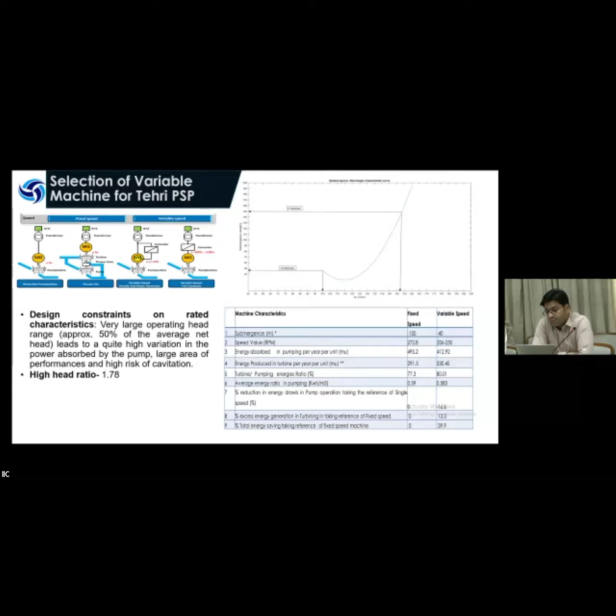Means in the case of fixed speed machines, we would have to excavate the powerhouse up to 250 meters for the setting of the turbine. By using variable speed machines, the submergence is only 40 meters. Also, the head ratio is 1.78. As per the report published by the CEA, variable speed machines are to be used for a head ratio of more than 1.35. Also, because of variable speed machines, we have an improved cycle efficiency of 80.01%, and savings in energy during both pumping and generation.